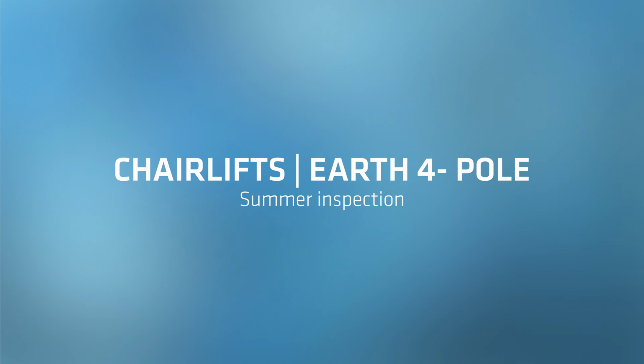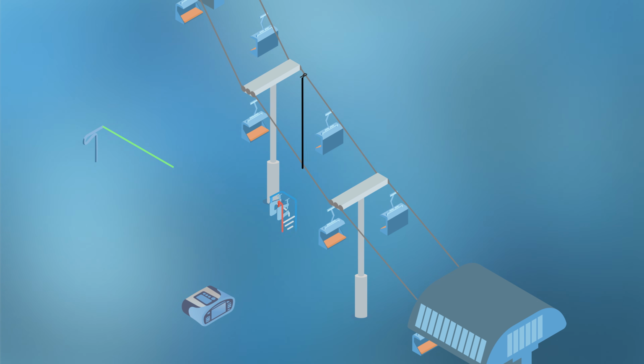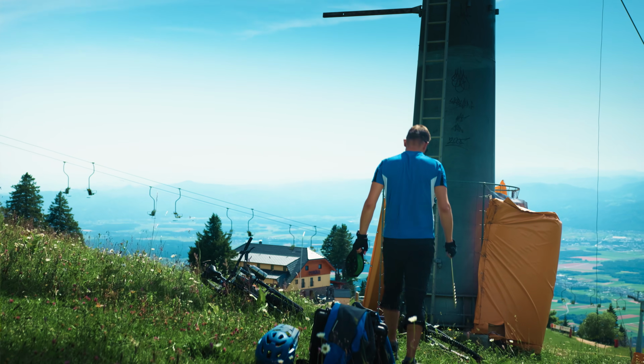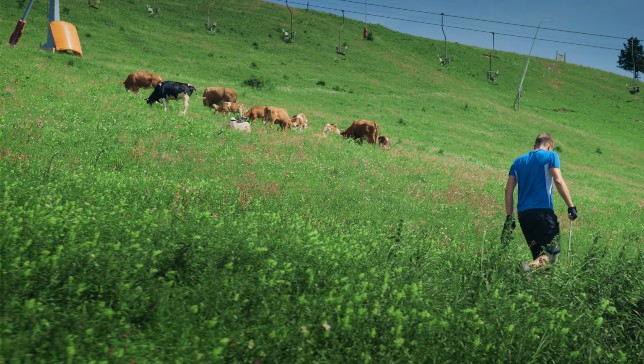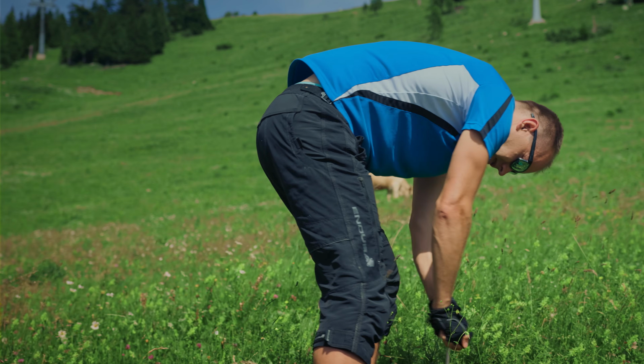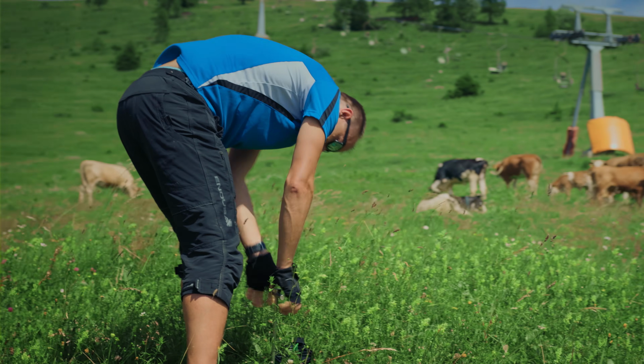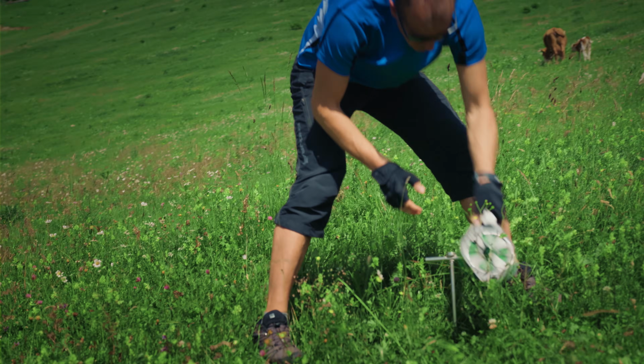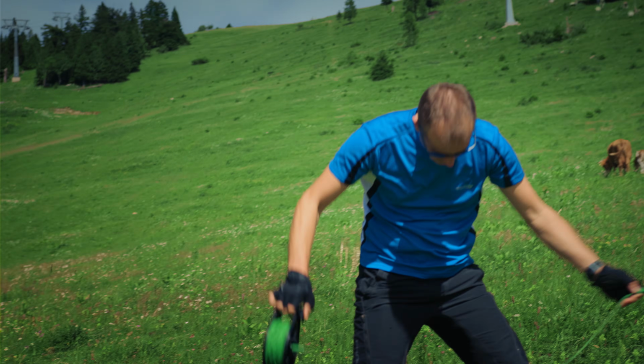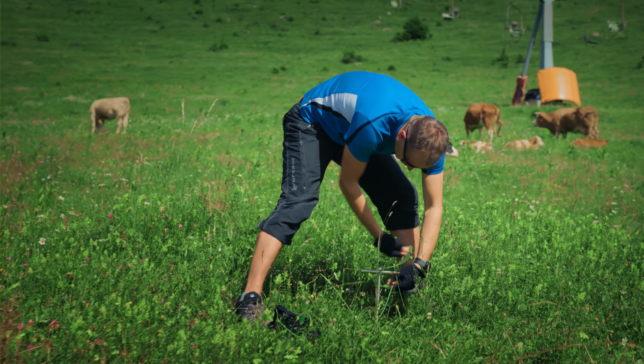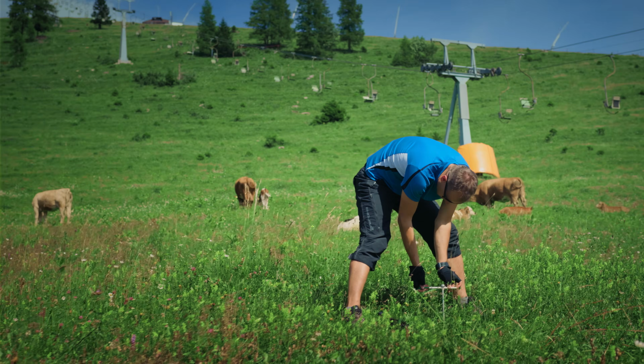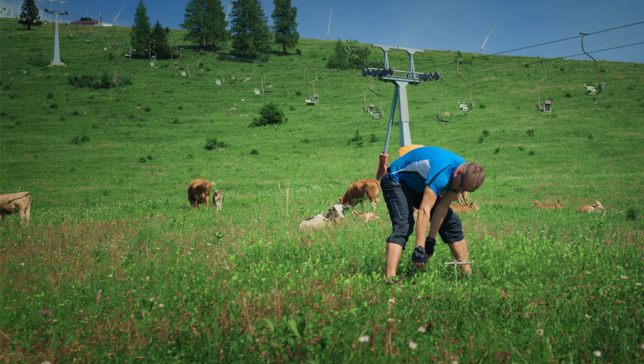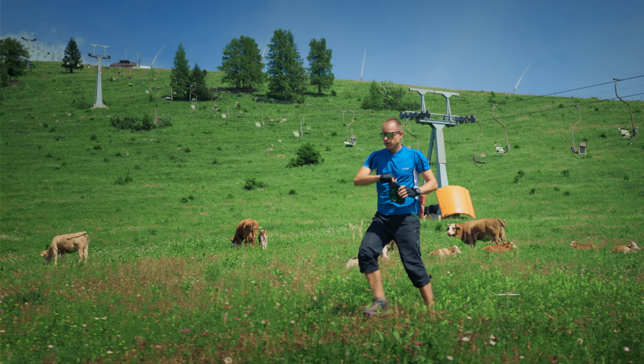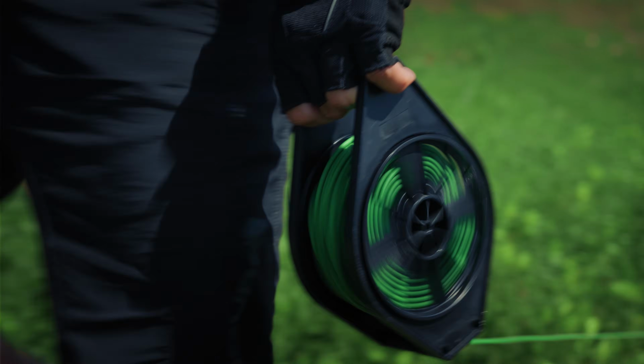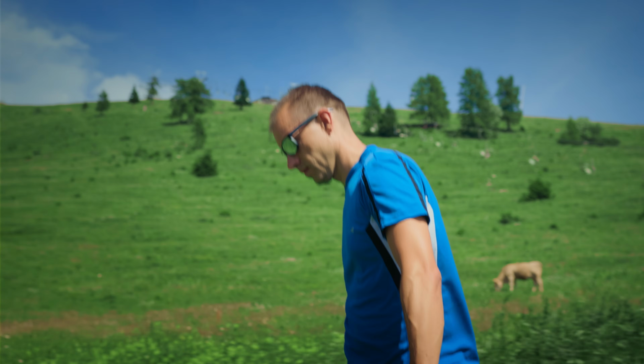Grounding resistance measurements not performed during the winter period may additionally be carried out during summer inspections. After testing for touch and step voltages, we extend the setup using a 50-meter measuring lead and a probe from the equipment kit.